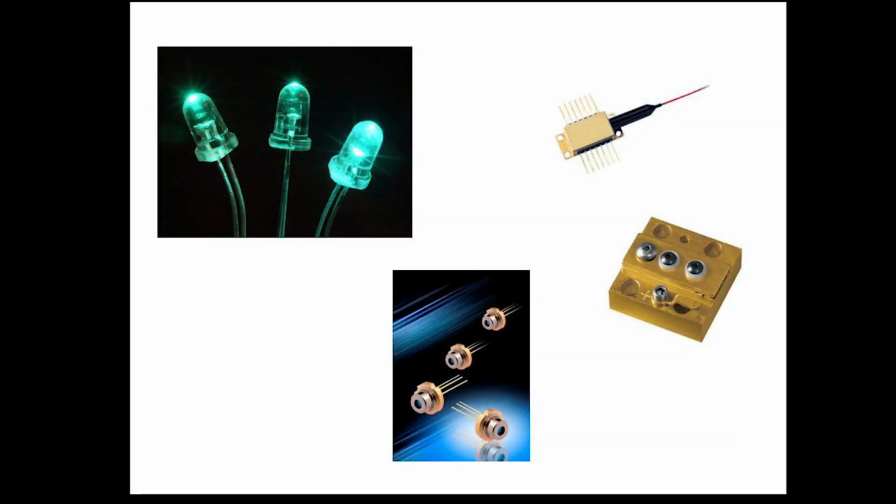Because this optical trick makes the readings independent of beam size, position, and divergence, we can use an integrating sphere to measure power from sources whose beams are widely diverging, such as LEDs, VCSELs, and other laser diodes, fiber optics, lamps.